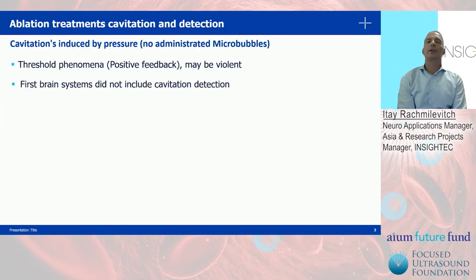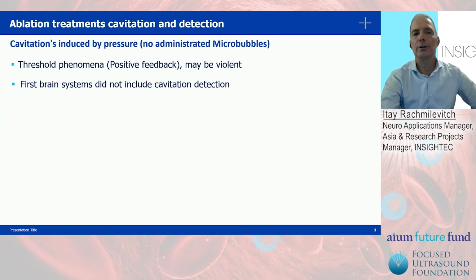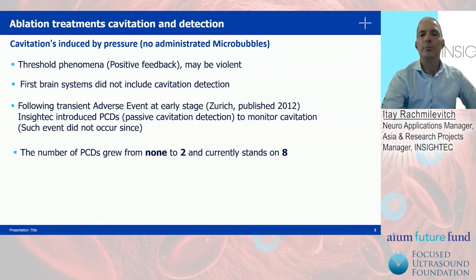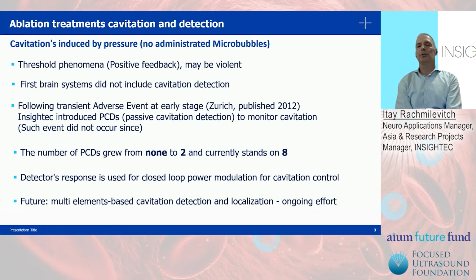The role of cavitation saw a significant change and growth within the recent 10 years, so to say. Cavitation is, of course, a threshold phenomenon. Positive feedback may be violent, can be used, but should also be taken care of. In our first brain treatments, we actually did not use cavitation detectors. It was not before a very early stage, when Professor Daniel Germonot of Zurich published his case report of an adverse event, that we realized that cavitation detectors should be introduced to the system. We then first introduced 2 cavitation detectors, and over the years we have added more.